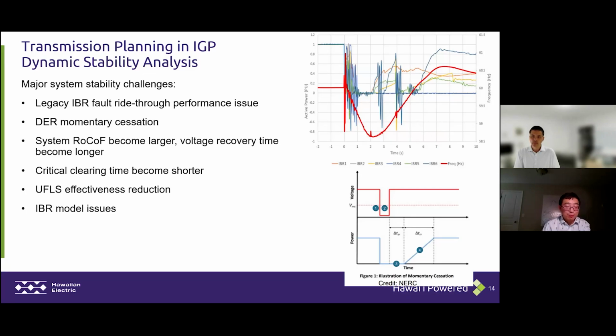And since we have firm machine dispatch that is less or retired, we do see in the study that rate of change of frequency, RoCoF, could become much larger than what we see in real life events. And we also see the critical clearing time become shorter. We're going to need communication, dual pilot communication, or more transmission lines to avoid zone 2 clearing. And with DER penetration level increasing everywhere, we also see that our under-frequency load shedding system effectiveness is reduced.